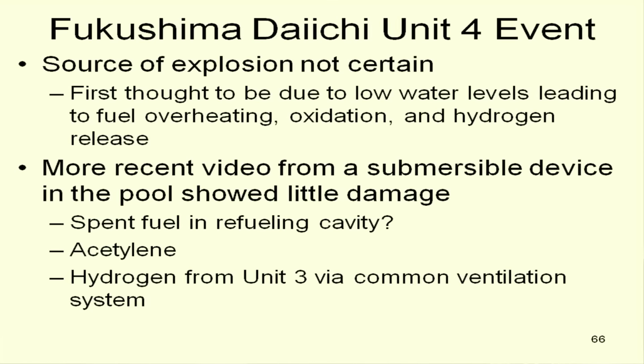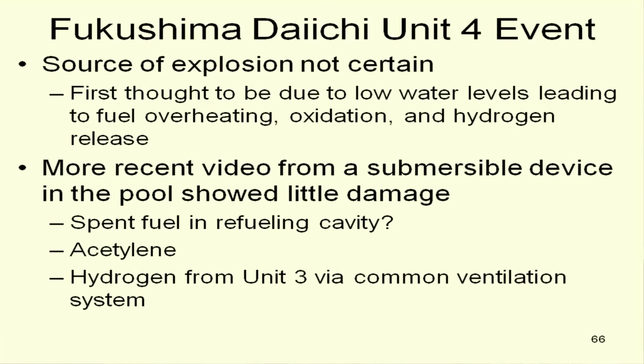Other than that, on the site, we believe there have been problems in the units 1 through 3 spent fuel pools with losing some water, coming uncovered and overheating. But that's not certain because inside of those reactors, it's very radioactive, and they just haven't been able to get there yet and do the inspections. They've had some remote pictures of it, but you look at a pool, it looks like a junkyard or something. You just can't see anything.